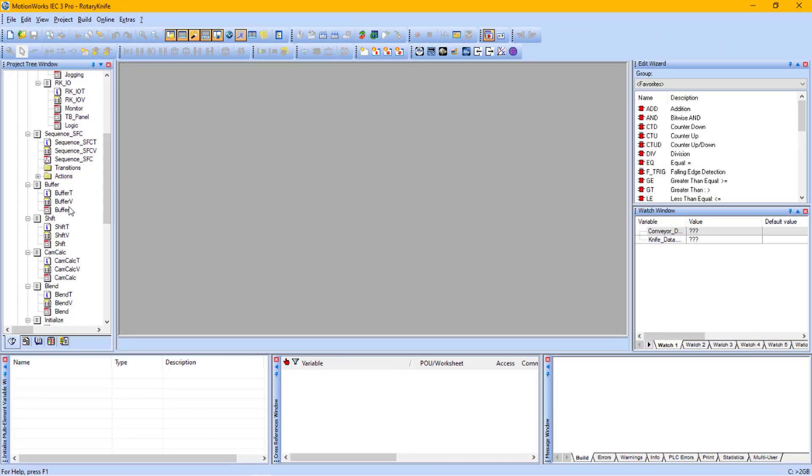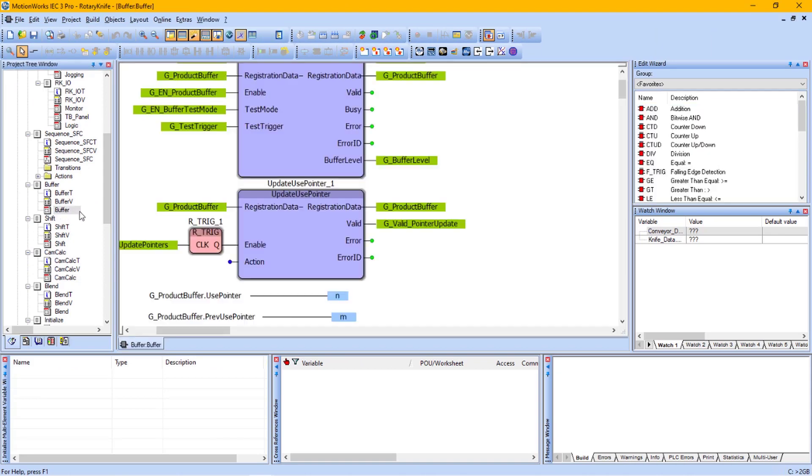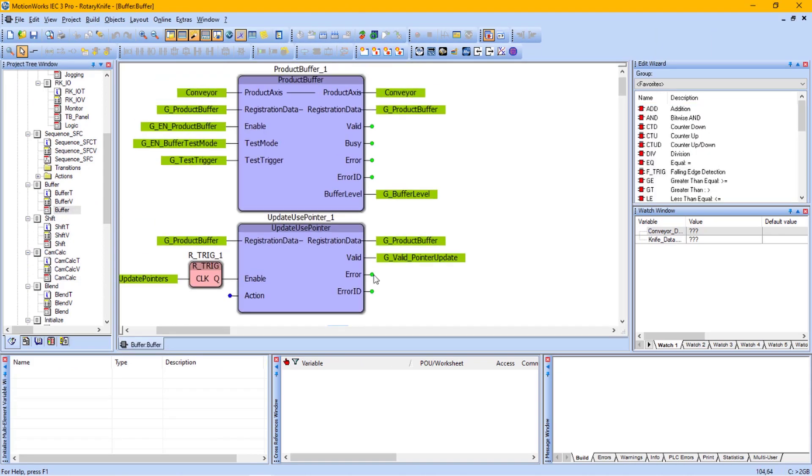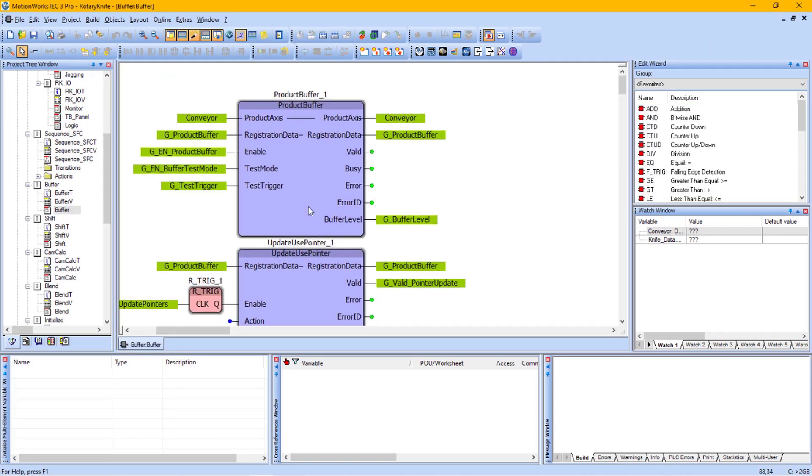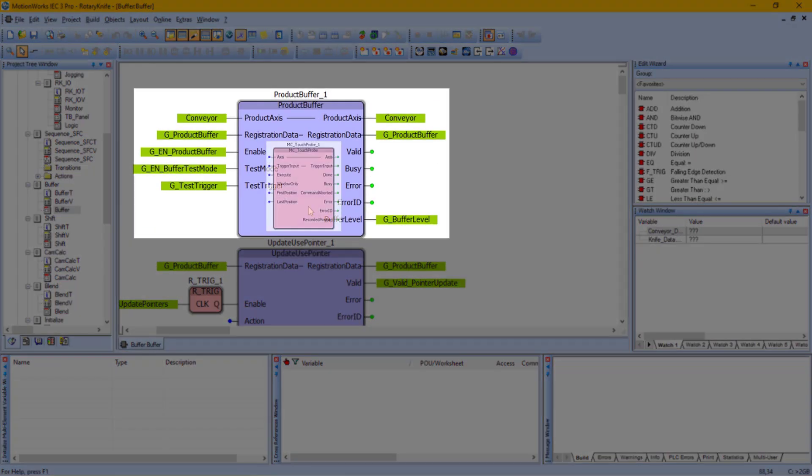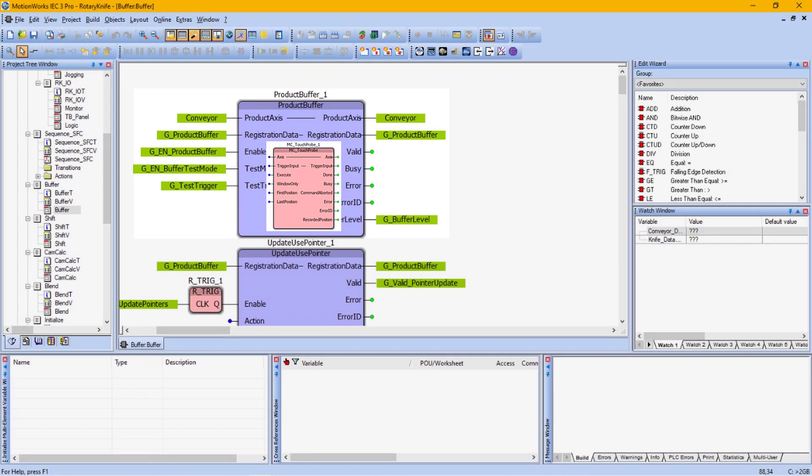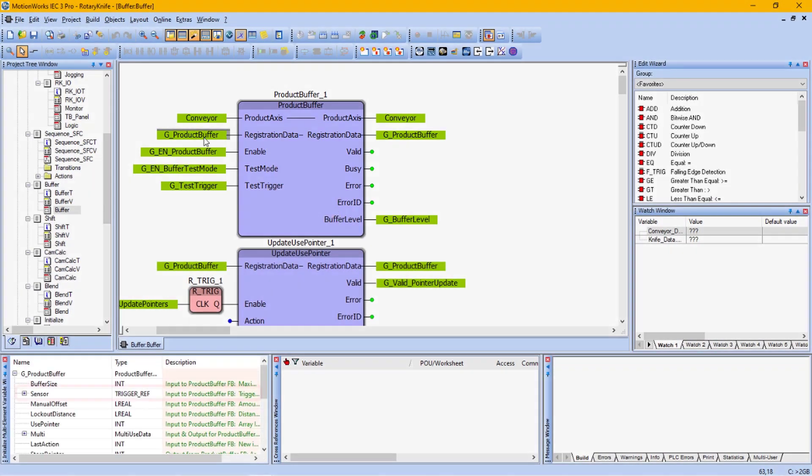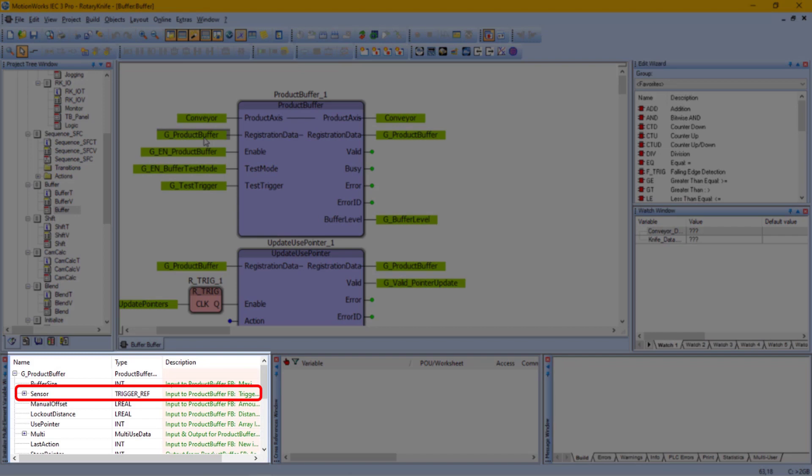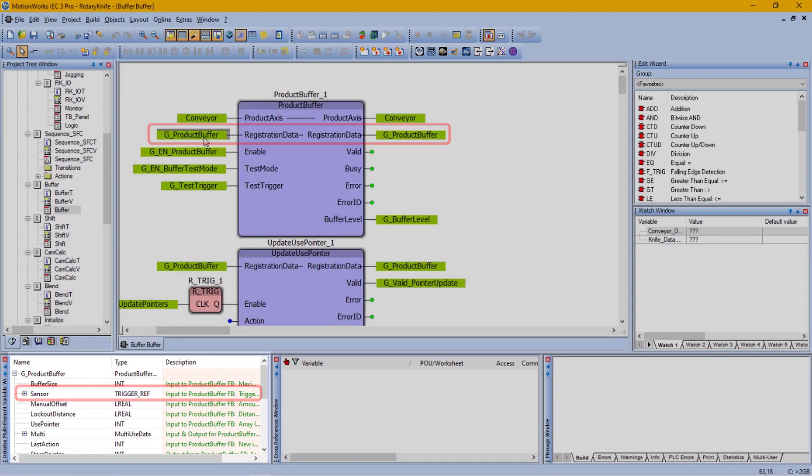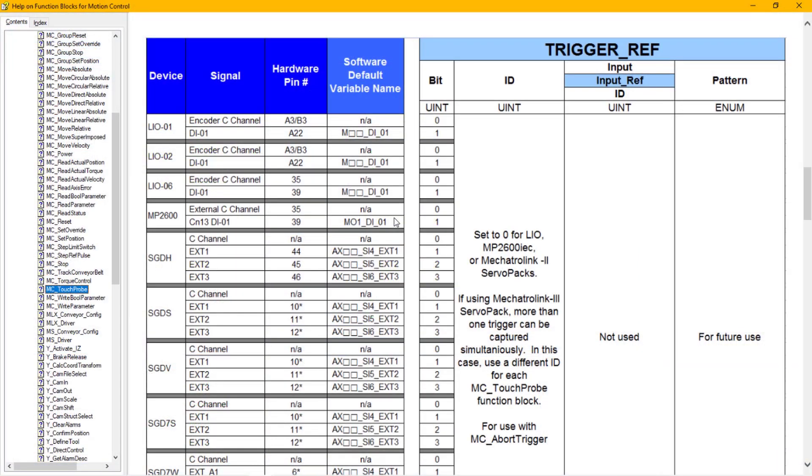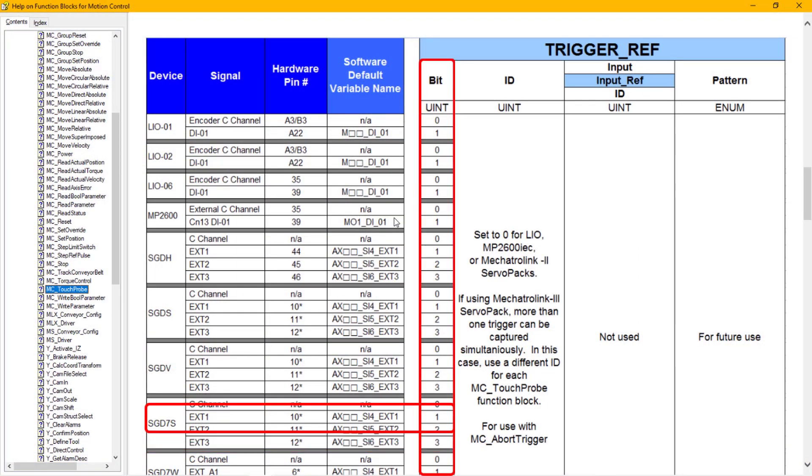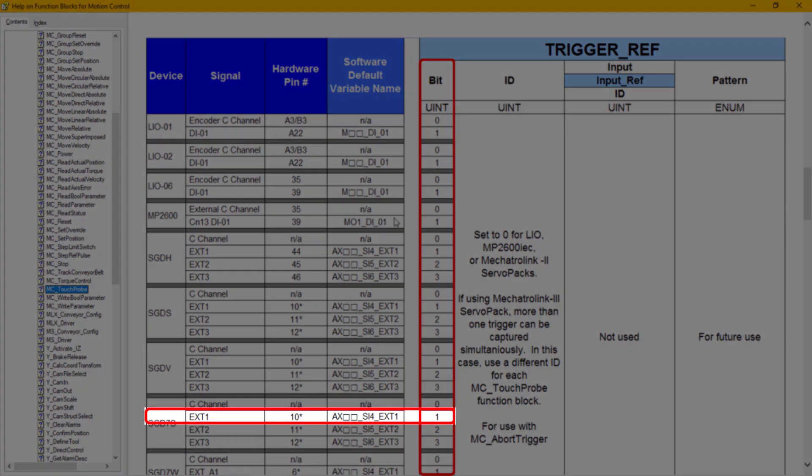Going into the buffer POU, the product buffer function block uses the touch probe function block internally to capture the tape positions on the belt. The trigger ref input in the registration data needs to be adjusted to use the EXT1 input. Looking at the touch probe help, I need to set the bit element of the trigger ref structure to 1 to use the EXT1 input.